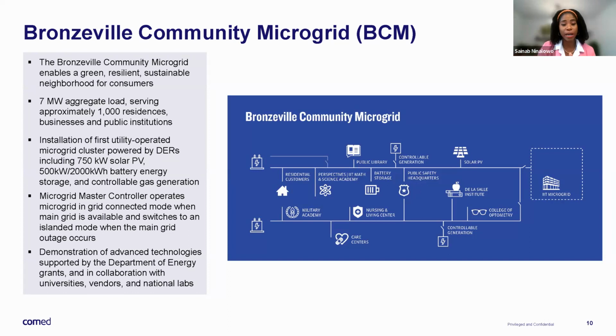What's complex about this controller is that it's being put into a grid system that's already built out. We have voltage optimization capacitor banks, distribution automation devices, and other grid edge devices on the grid today. The controller has to work in unison with these to optimize the DER assets within the microgrid, so we can island autonomously without impacting customers within the microgrid.